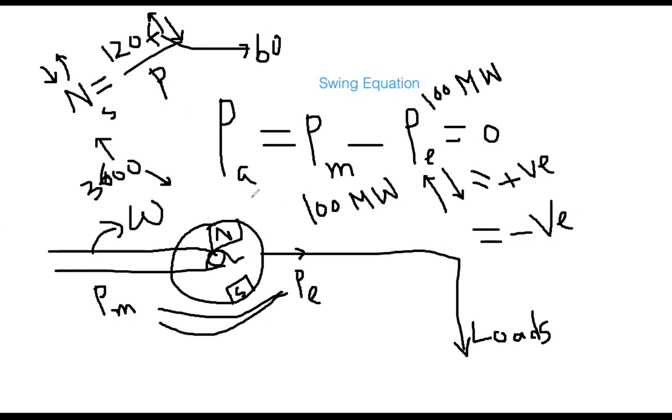So now the question is, when you are injecting load or taking out load as a customer, what is the tolerance? The United States tolerance is plus minus 3% of the 60 Hertz. So you can calculate that it can go a little bit upward or downward. If it goes much more upward or much more down than this number, then that is a frequency stability problem.